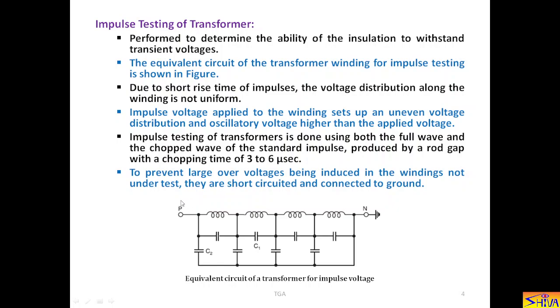To prevent large overvoltages being induced in the winding not under test, they are short circuited and connected to the ground. If they are open circuited, then voltage will be induced in those windings.